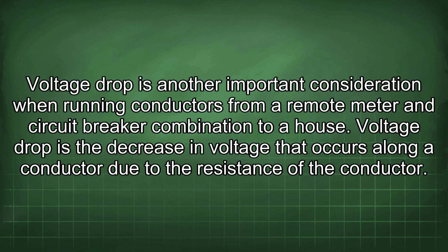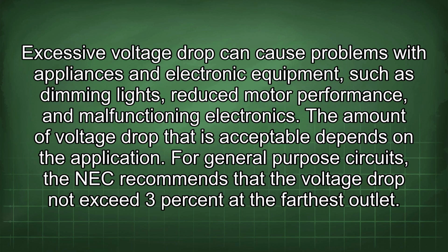Voltage drop is another important consideration when running conductors from a remote meter and circuit breaker combination to a house. Voltage drop is the decrease in voltage that occurs along a conductor due to the resistance of the conductor. Excessive voltage drop can cause problems with appliances and electronic equipment, such as dimming lights, reduced motor performance, and malfunctioning electronics. The amount of voltage drop that is acceptable depends on the application.